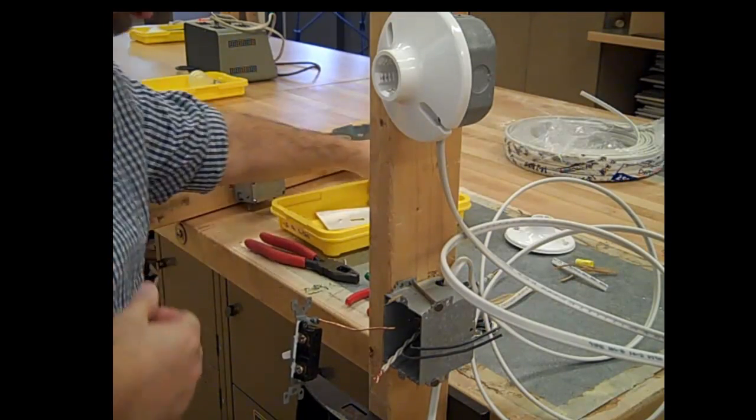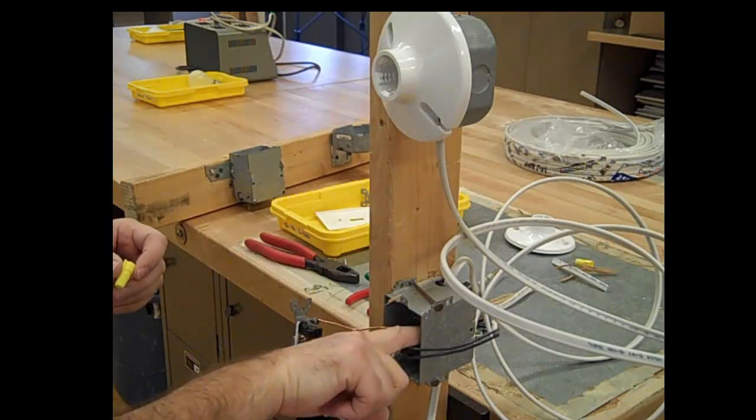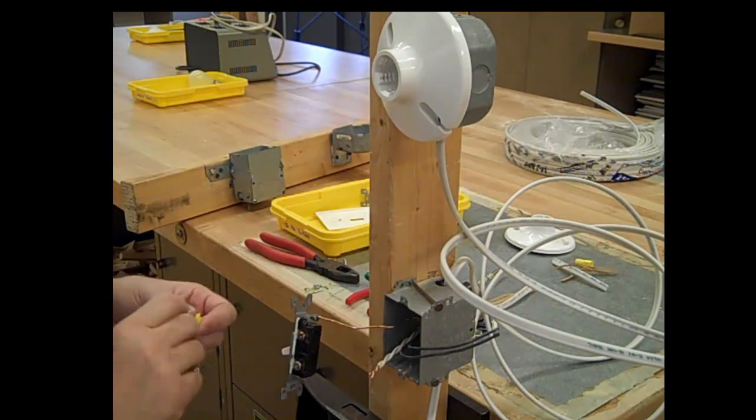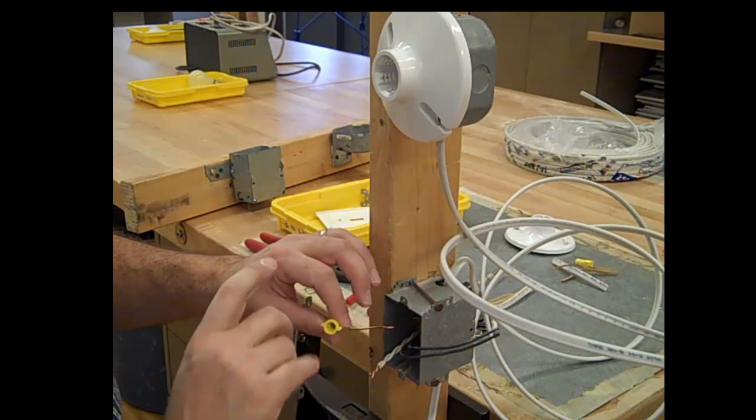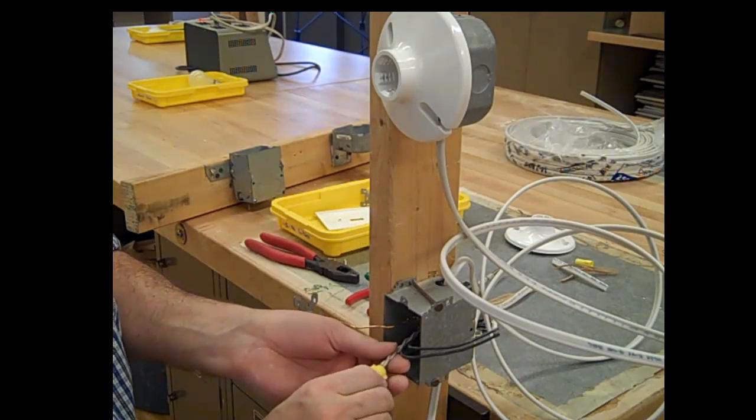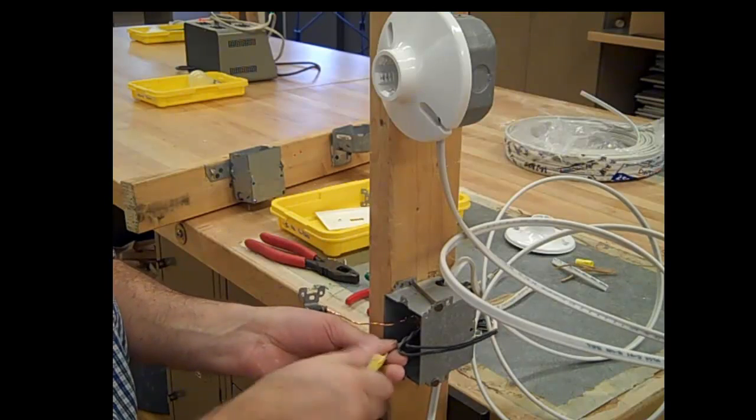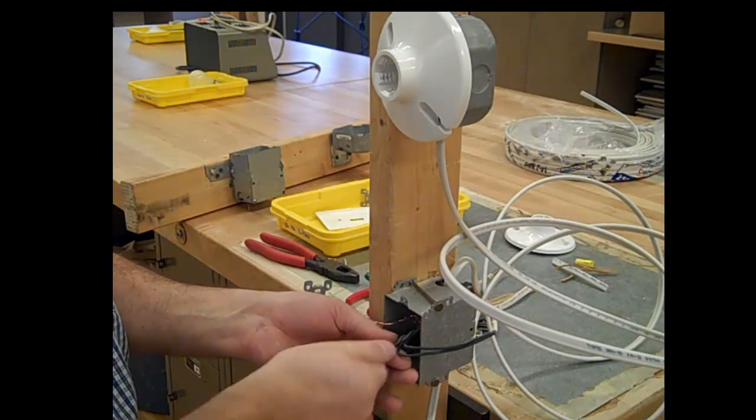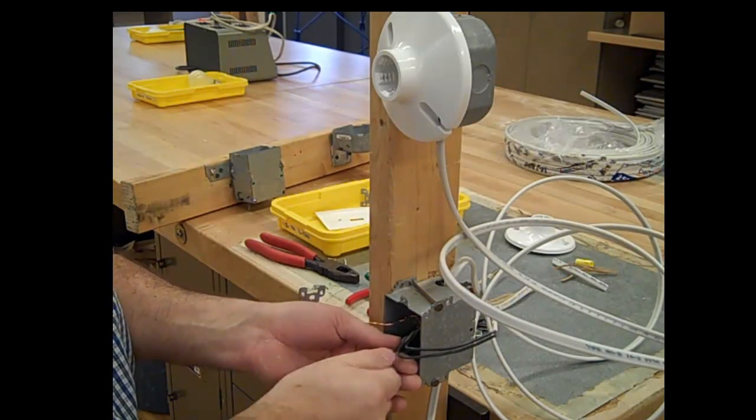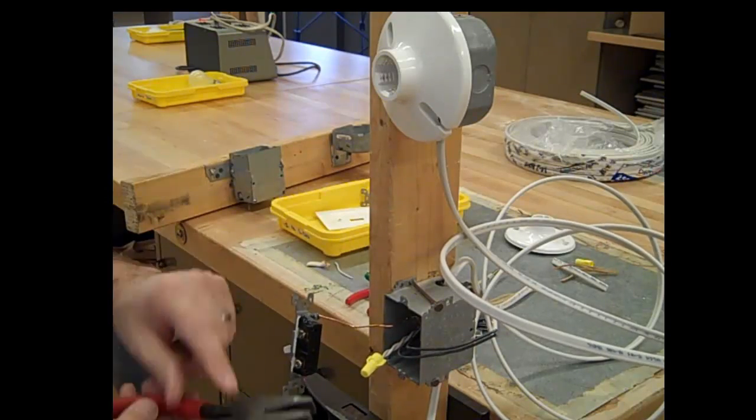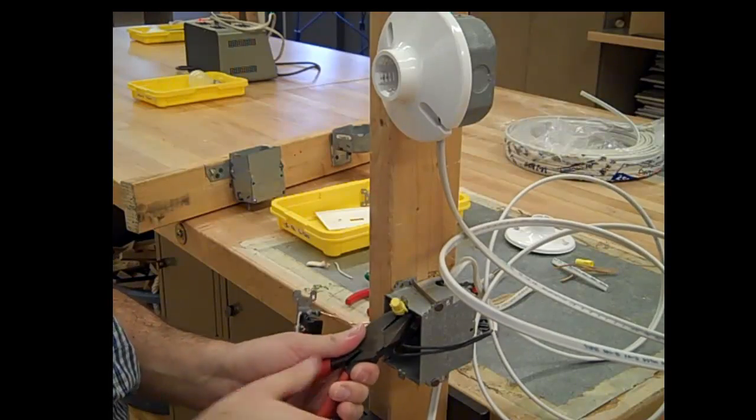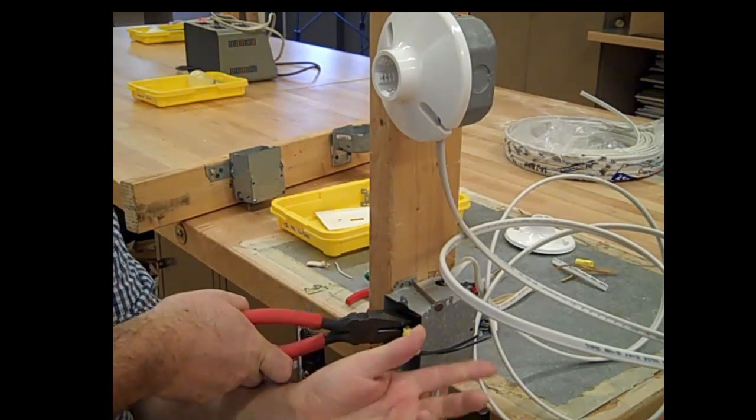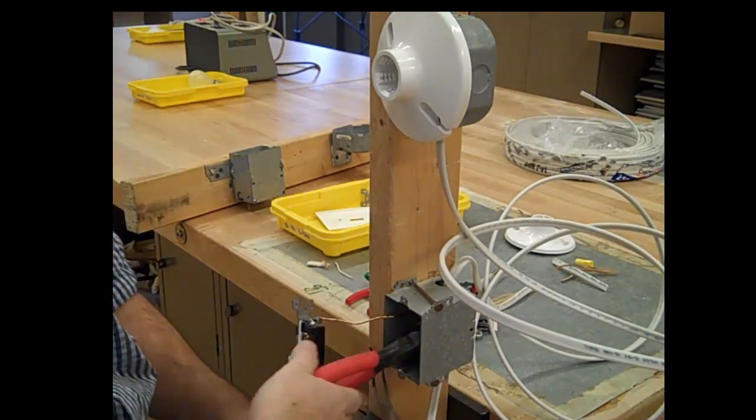You use a wire nut. There is a metal spring on the inside of here that wraps around these and makes a very good connection. Twist this on until you can't twist it anymore. Take your pliers, grab onto the wire, twist and push it all the way to the back of the box.